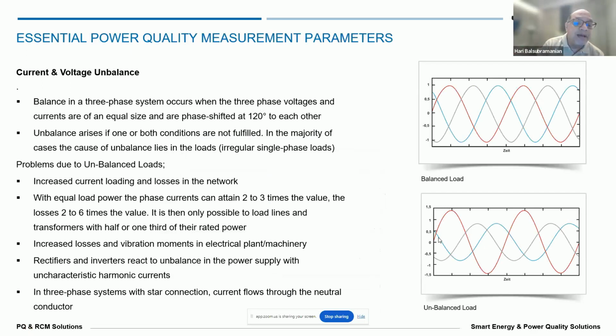Current and voltage imbalance is the next topic. This is again about the phase shift not being 120 degrees, or the current not being equal in all three phases, or the voltage not being equal in all three phases. This can have an effect on the systems as well. There are ways to ascertain the percentage unbalance in the voltage and the current, and then we can take action based on that.